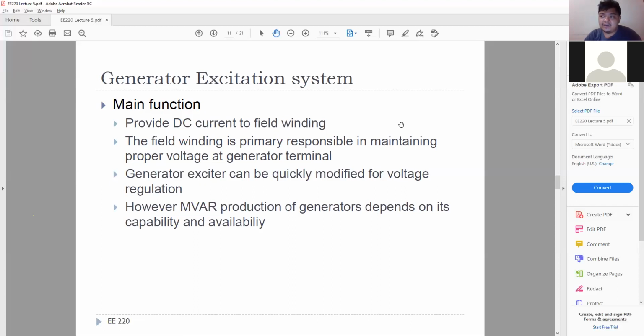For example, if it's a 300 megawatt generator, there's usually a convention we call the D curve. It's like an estimate. When it's operating at full capacity, it can operate at an inductive MVAR of 0.8 of its full capacity, so 300 times 0.8.